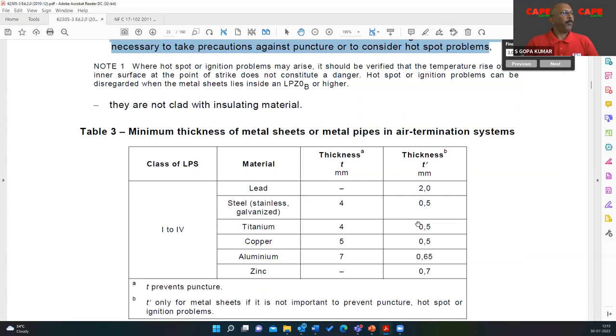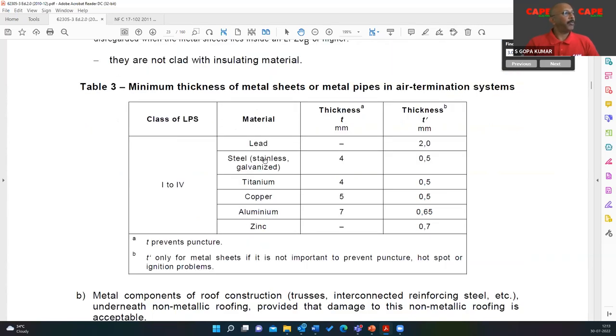Now, in this particular case, for example, we don't use lead, titanium and all. We use galvalume sheet or stainless steel material. Now, if the thickness of the metal is more than 4 millimeters, which is rare, of course, where these are used, sometimes the oil storage tanks. So if the thickness of the metal is more than 4 millimeters, lightning cannot puncture this material. And you can use that tank itself as your air termination.